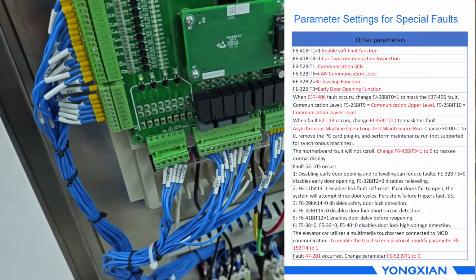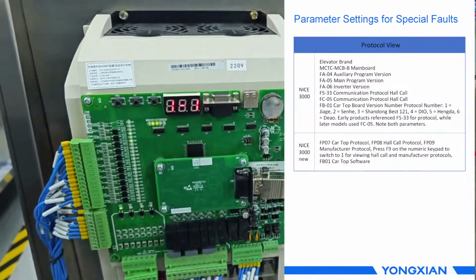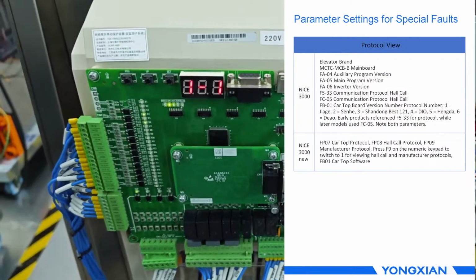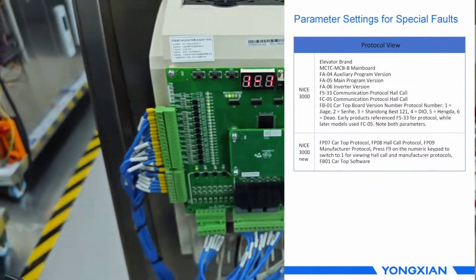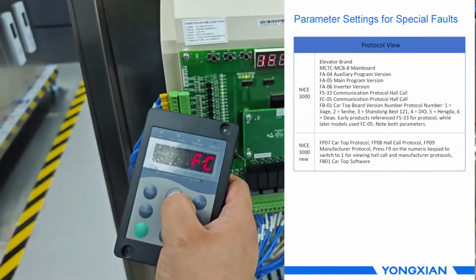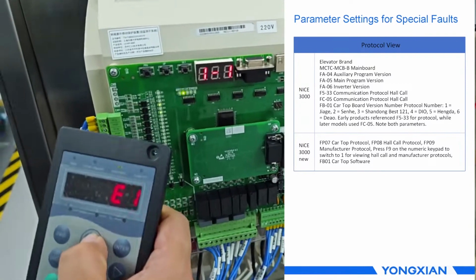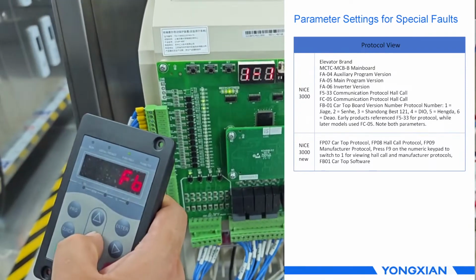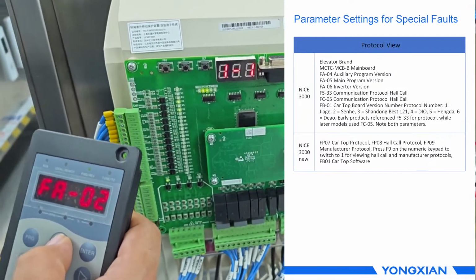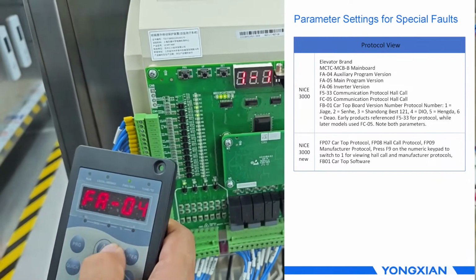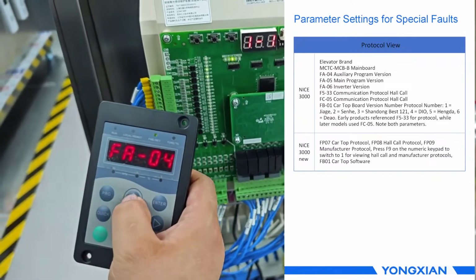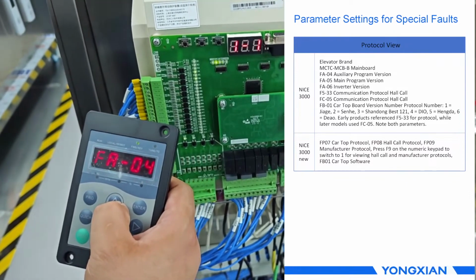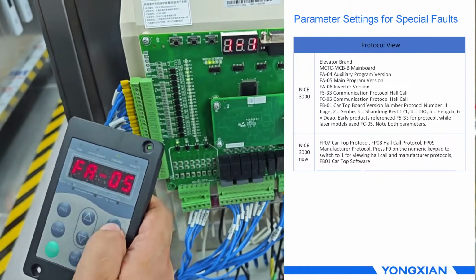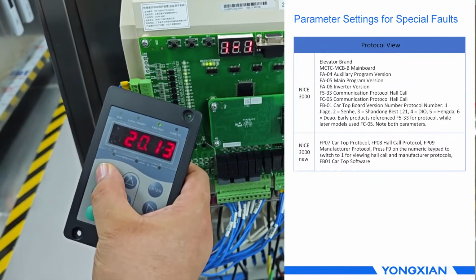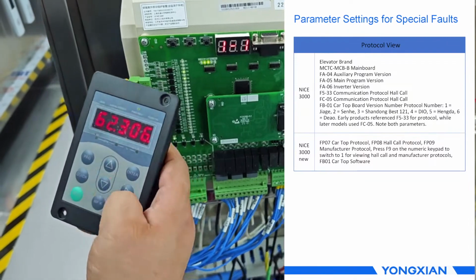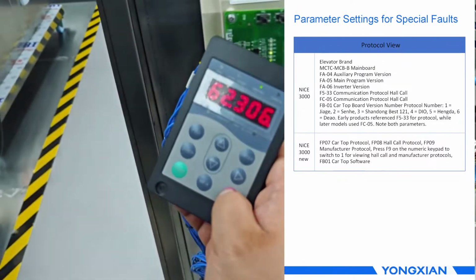Next, let's look at the protocols to check when changing some mainboards. If it is the old 3000 or old 3000B mainboard, FA-04 is the auxiliary program version, FA-05 is the main program version, and FA-06 is the inverter version.